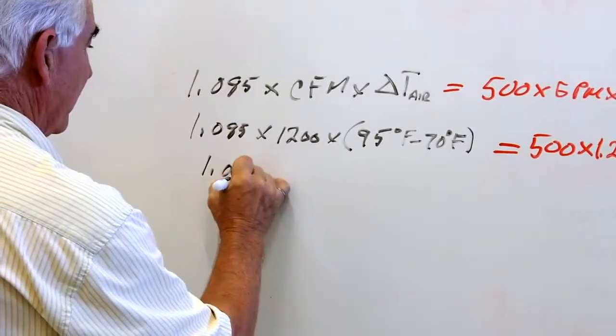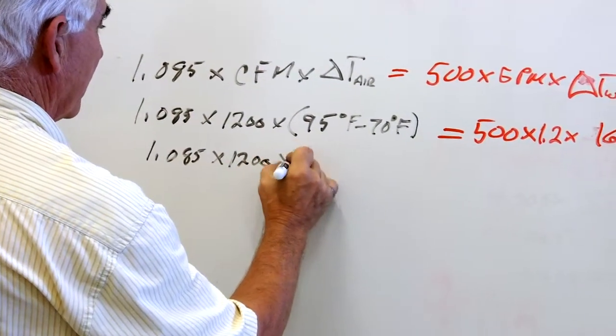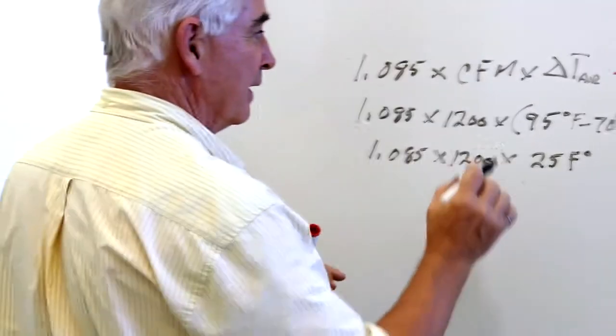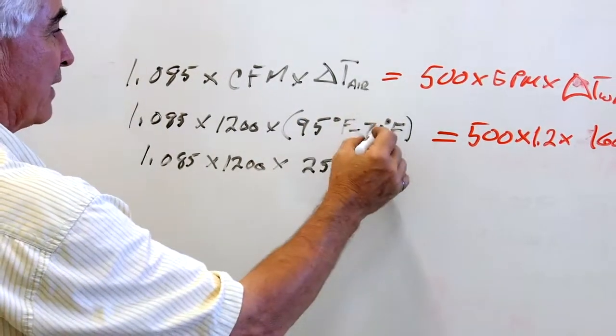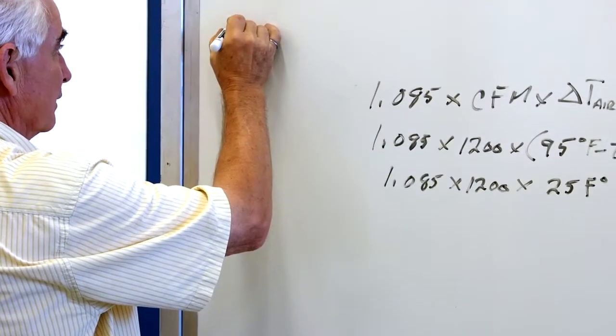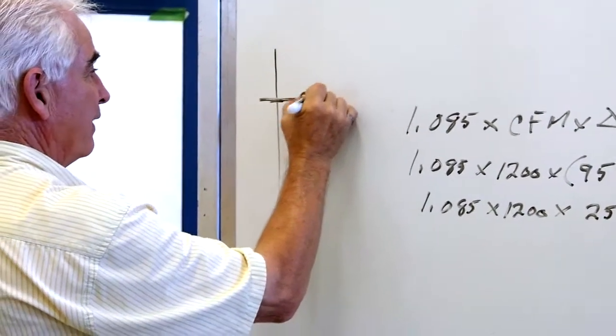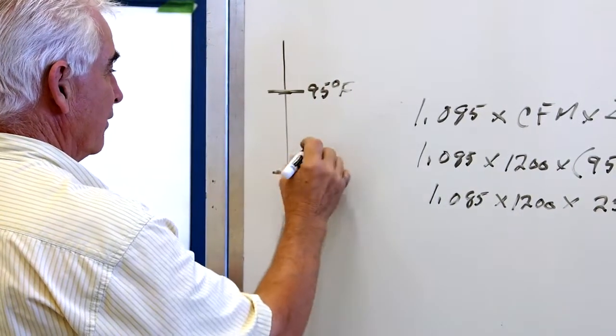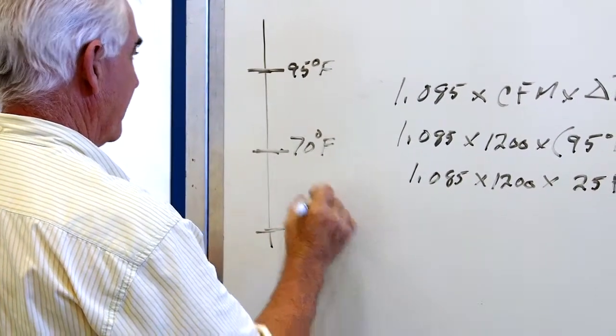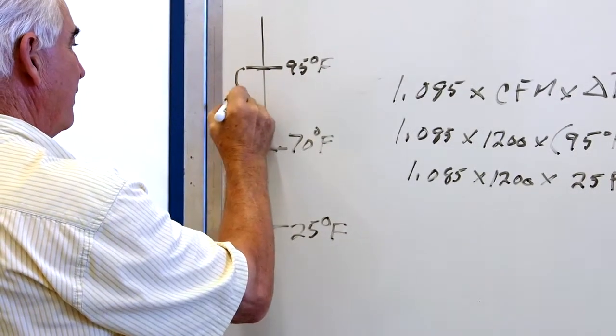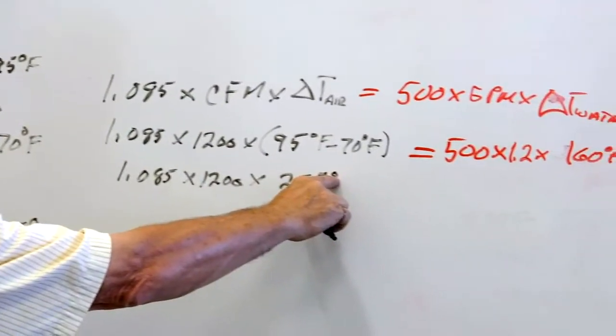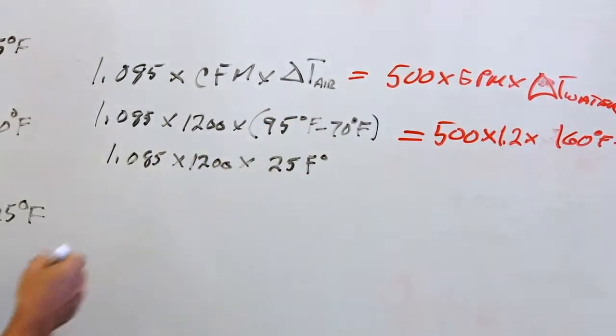We can simplify: 1.085 times 1200 times 25 Fahrenheit degrees. Note the difference — 95 degrees Fahrenheit minus 70 degrees Fahrenheit is 25 Fahrenheit degrees. Looking at a thermometer, 95°F is here and 70°F is here — that difference is 25 Fahrenheit degrees. When expressing a temperature difference, the degree symbol follows Fahrenheit; when expressing a measured temperature, it comes before.